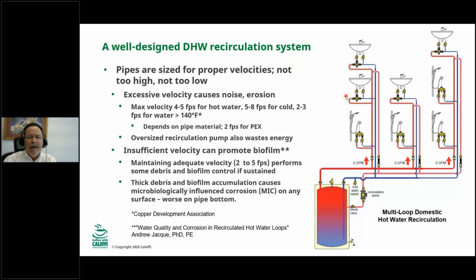Good. All right, now what about velocities that are too low? Another person in our industry who's an expert reference is Andrew Jacque, and he sent me this information about maintaining adequate velocity to perform some debris and biofilm control. So you want enough velocity to keep that water moving. If it's going too slow and you have laminar flow, then you can have thick debris and biofilm accumulation. That causes something called microbiologically influenced corrosion, or MIC, on the surface, and it's actually worse on the bottom. So really low velocity isn't good either.